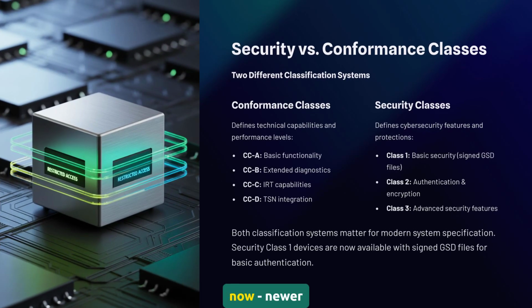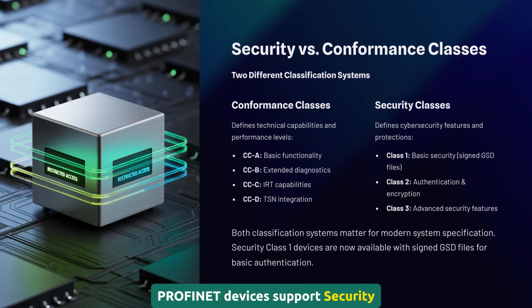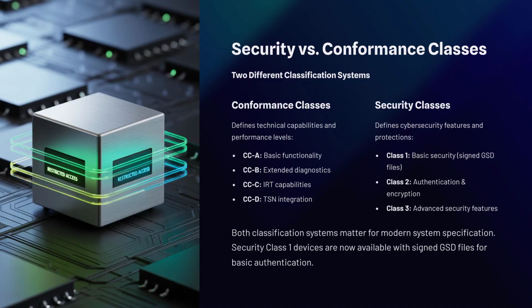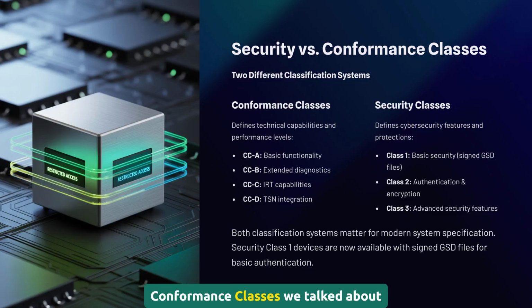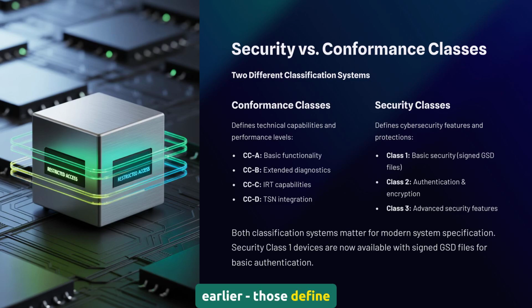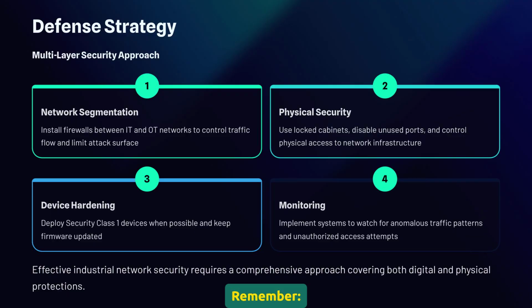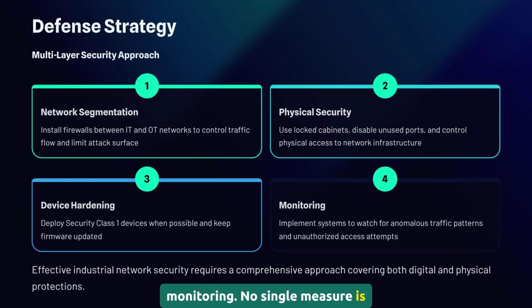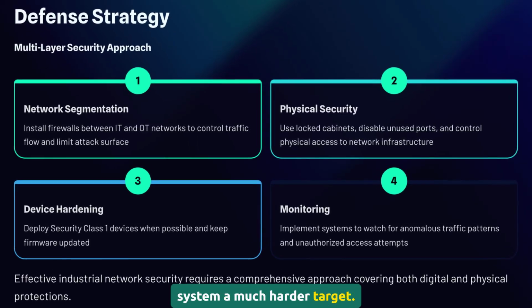And here's what's available now. Newer PROFINET devices support security classes with signed configuration files and secure commissioning. When you're specifying new equipment, look for Security Class 1 certification. This is separate from the conformance classes we talked about earlier. Those define technical capabilities like CCA through CCD, while security classes define cybersecurity features. Both matter for modern systems. Remember, security is layers. Physical security, network segmentation, device hardening, and monitoring. No single measure is perfect, but together they make your system a much harder target.